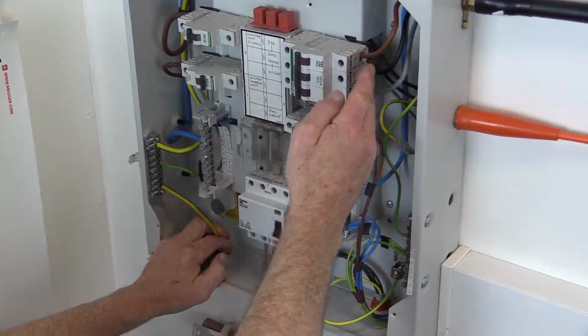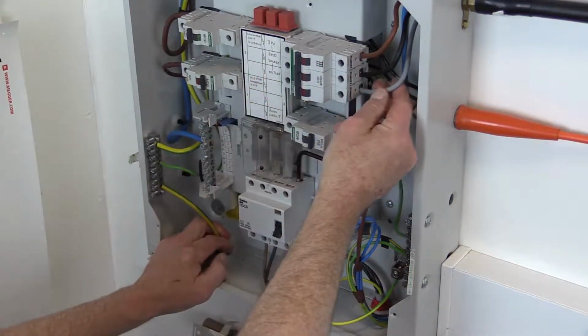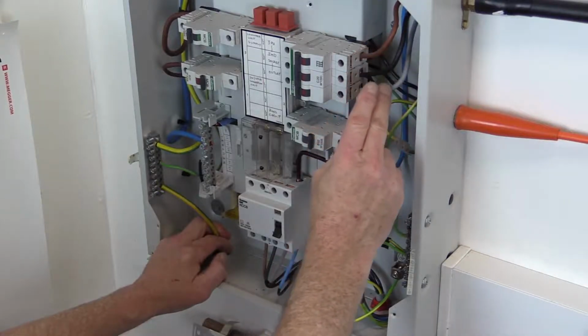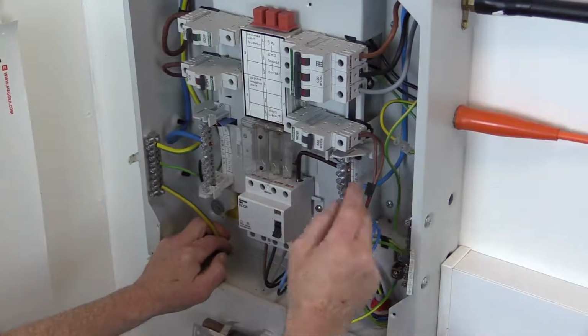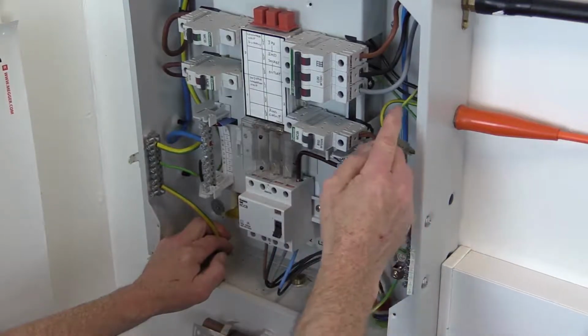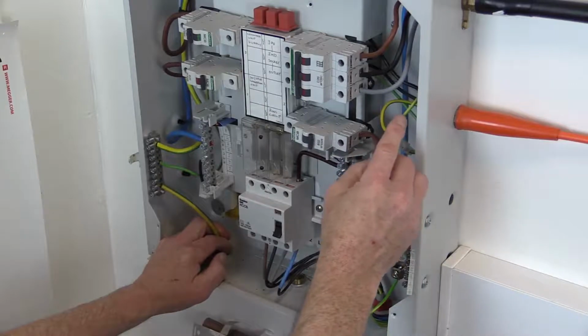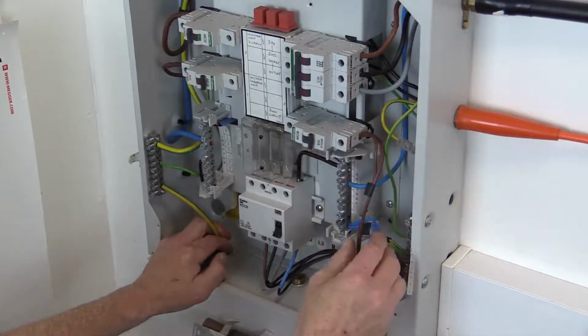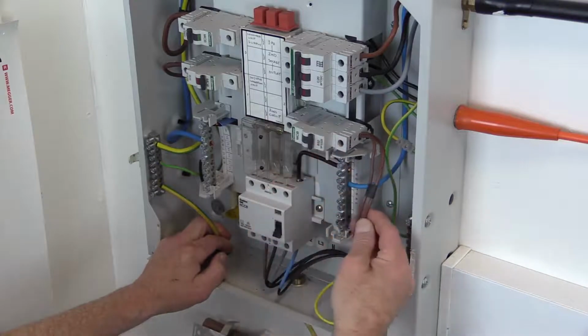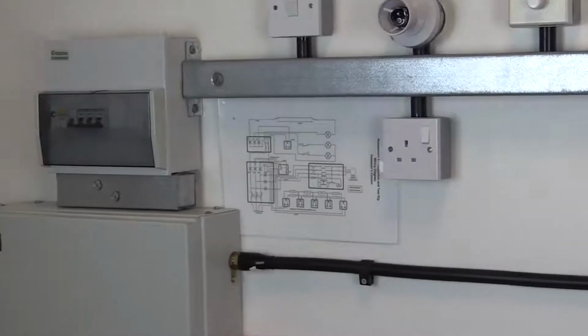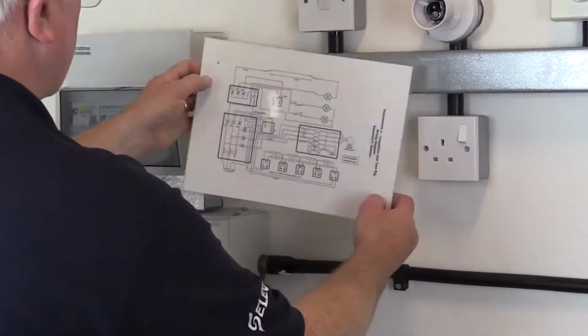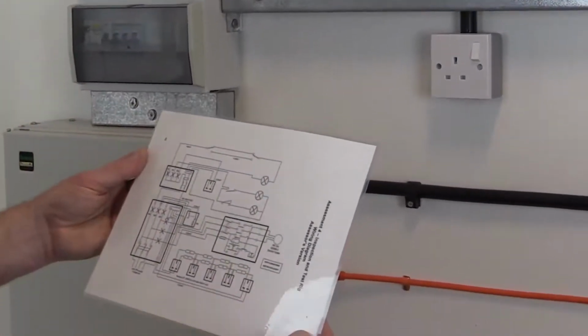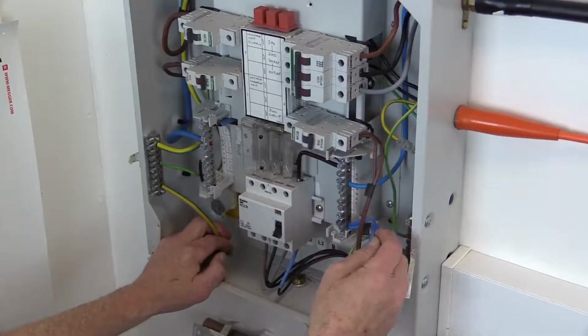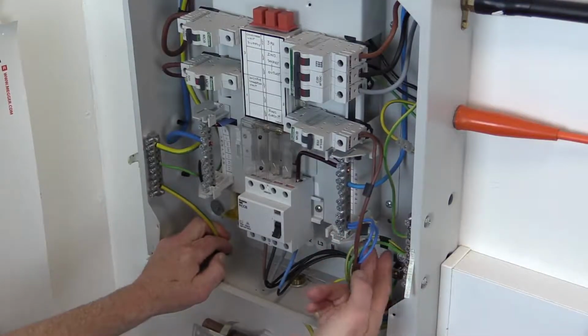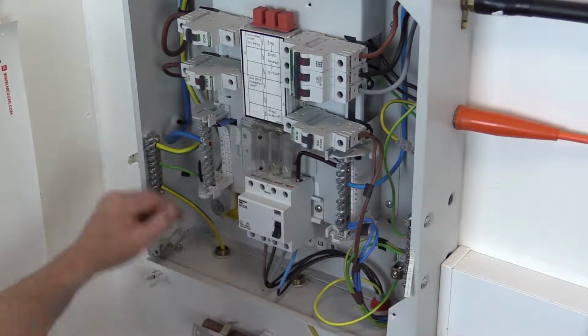Information will also be required to identify the type and composition of each circuit, conductor type and size, etc. Also the methods used for protection, basic and fault, and information necessary for the identification of devices for protection, isolation and switching, including its location, and also information on any circuit or equipment vulnerable to the tests. A schematic diagram for test rig 2 is available, identifying the final circuits, but inspection will have to be carried out to determine conductor sizes, method of protection, and information to identify the devices for protection.